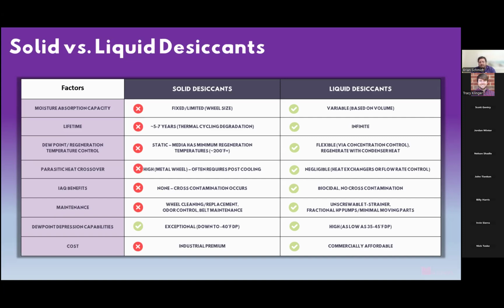Dewpoint capabilities. Solid desiccants do have exceptional dewpoint capabilities, very, very low. Liquid desiccants can get down to about 35 degrees on the bottom end, which is far better than traditional DX with hot gas reheat. But again, we really can't go below about 35 degree dew point. Cost-wise, as I mentioned before, liquid desiccants, especially Mojave, are really targeting the commercial DOAS market. We're really not trying to necessarily play in the same space as a solid desiccant, extreme low dew point type of system. They absolutely have their applications, but that does come at a cost premium.